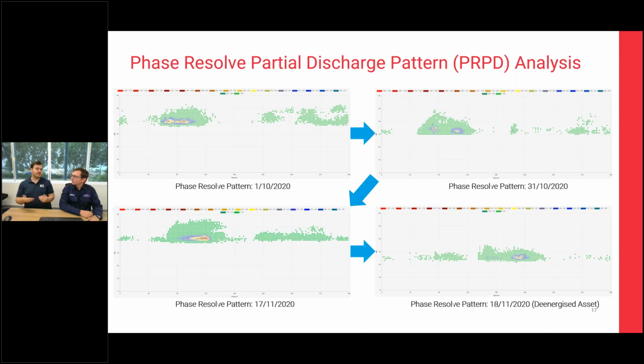There could be a number of reasons for this, and we discussed it a lot during the analysis. It could have been due to such high level signals that we were only picking up the right peaks. One of our leading theories is that there's a phenomenon in PD where discharge occurring very close to the conductor on the live portion, or right outside the insulation on the earth portion, causes a lopsided effect in the phase resolved patterns. When we looked at where the defect was, it's quite possible that was correct.